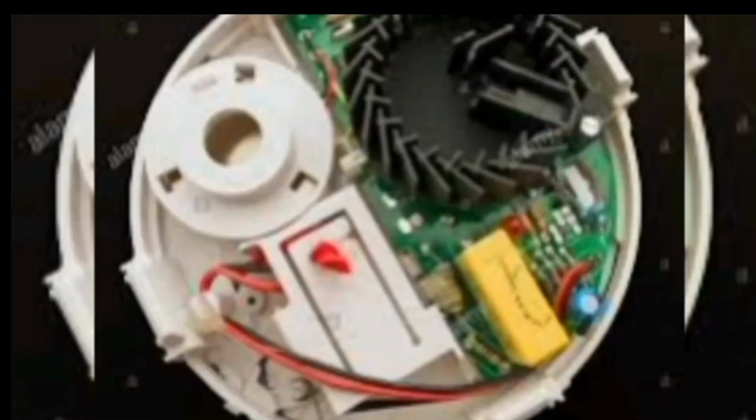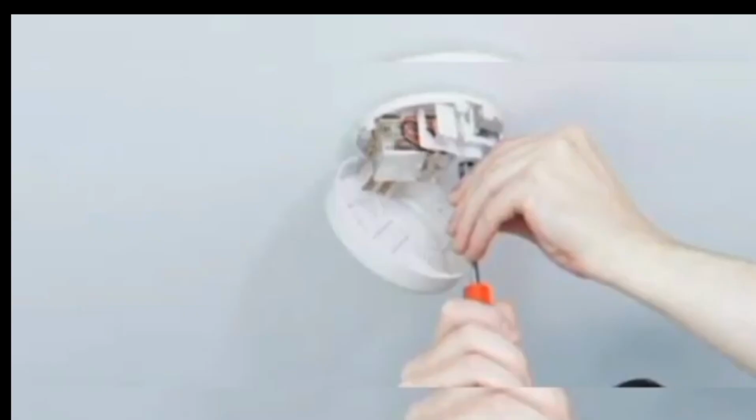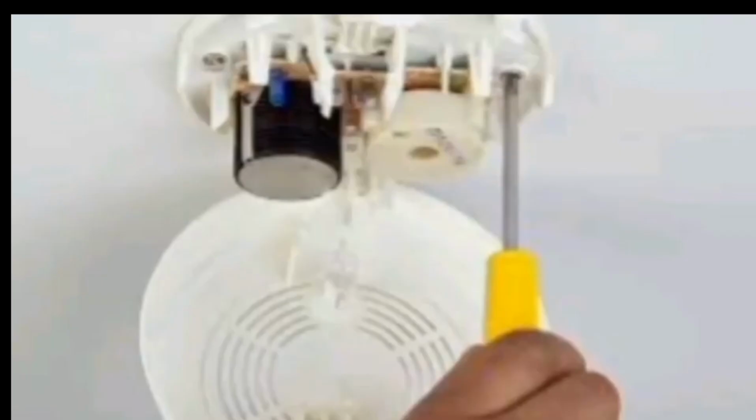To fix the smoke detector, you must first open it. Take the upper part, which generally contains 3 or 4 screw holes. Place it on the surface of the ceiling to make the marks. Fix it using the screw directly or using the dowels if it is a concrete slab. For wired smoke detectors, simply connect the cable and the installation is complete.